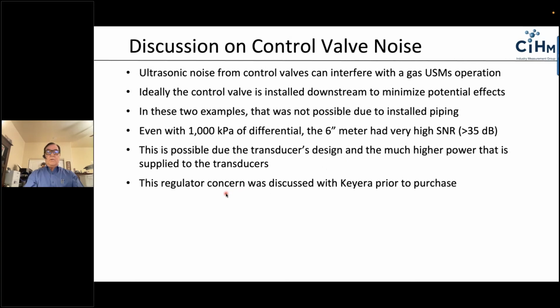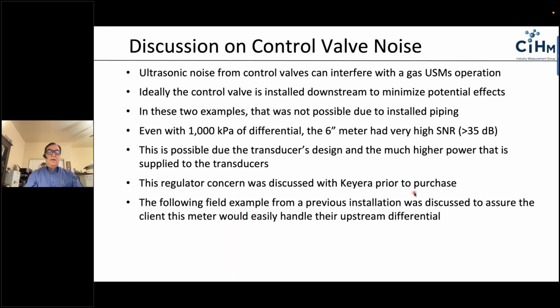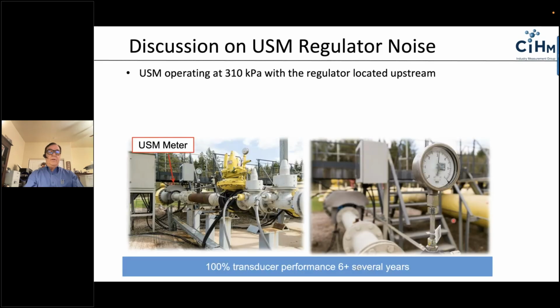So the concern about the regulator was discussed with Brad and Brian before the installation of this to assure them that the meter would continue working without a problem. And to do that, essentially what I'm going to show you is some data from a field installed meter in Europe where the regulator was installed upstream of the meter.